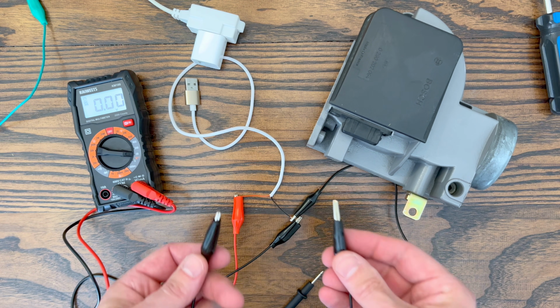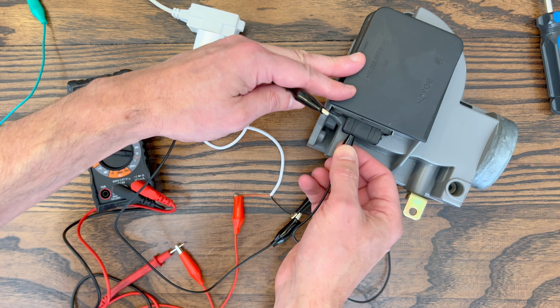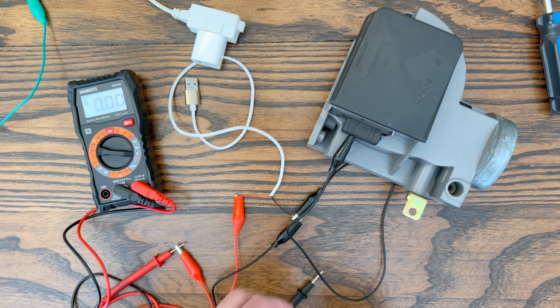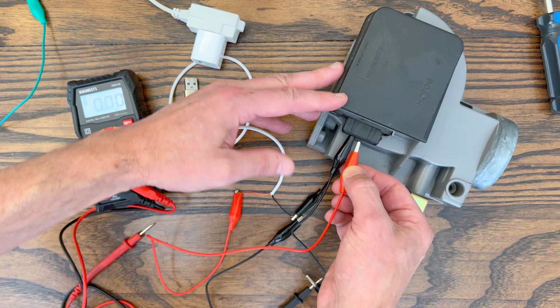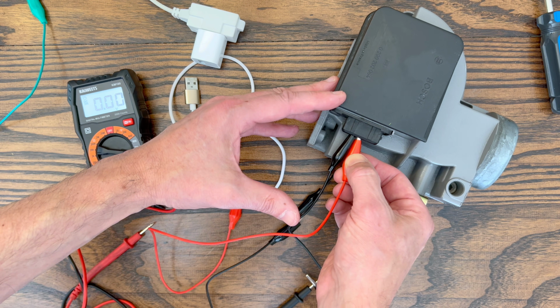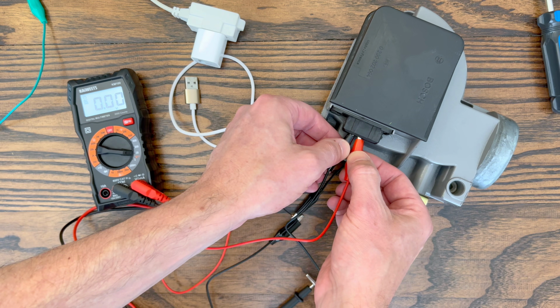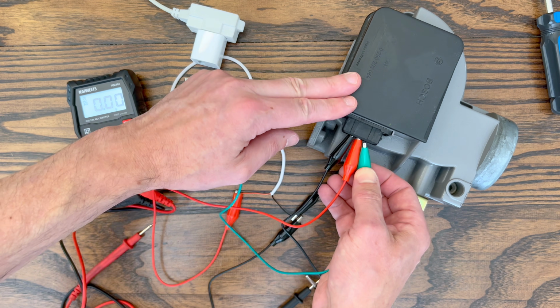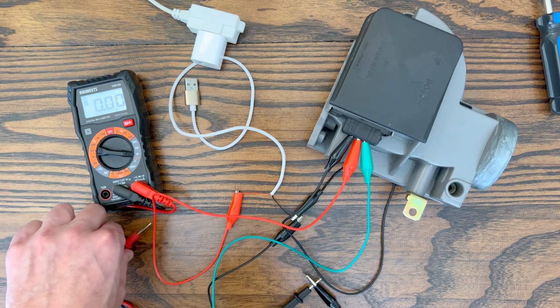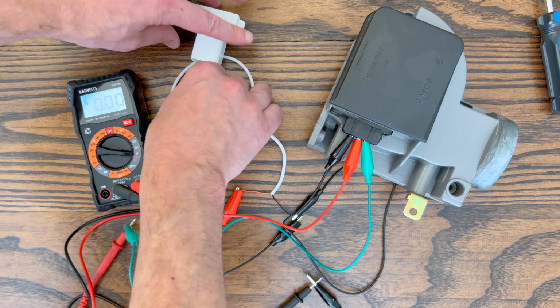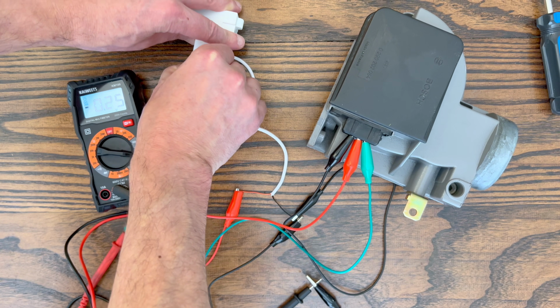The black ground wire from the charging cable is split into 2, with one lead connected to pin 4 on the AFM and the other connected to the negative probe on the voltmeter. The red positive wire from the charging cable connects to pin 3 on the AFM. Again, make sure these connections aren't touching each other. And finally, a lead is connected from pin 2 on the AFM to the positive probe on the voltmeter. With everything set up, the power can be reconnected, and it's time to take some readings.